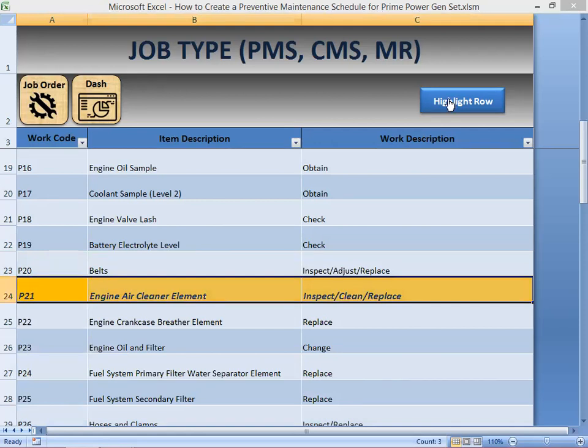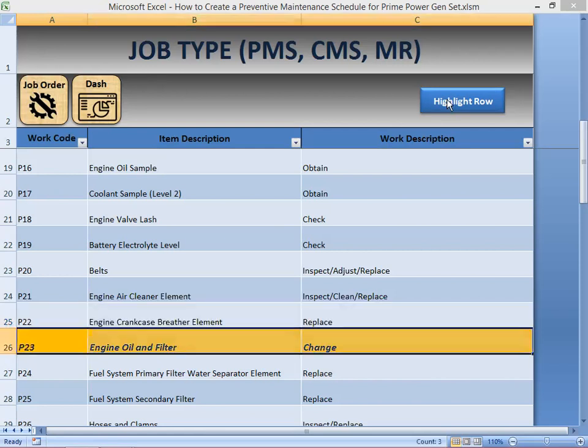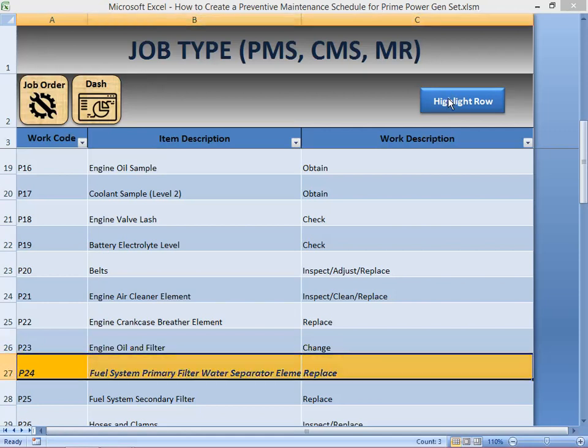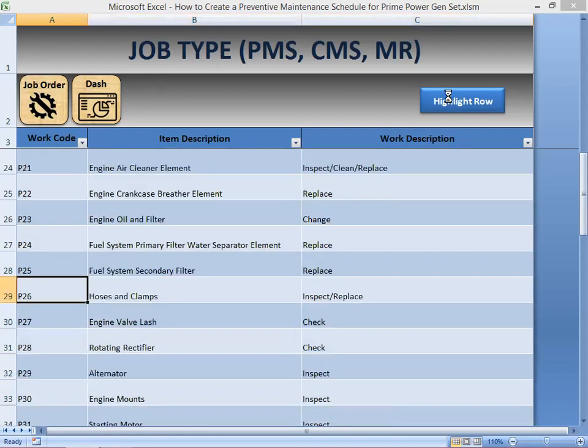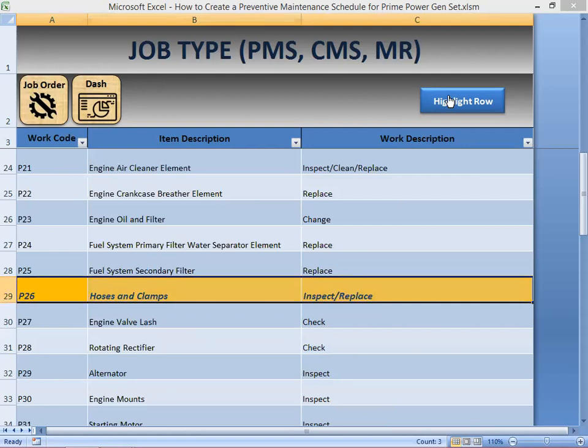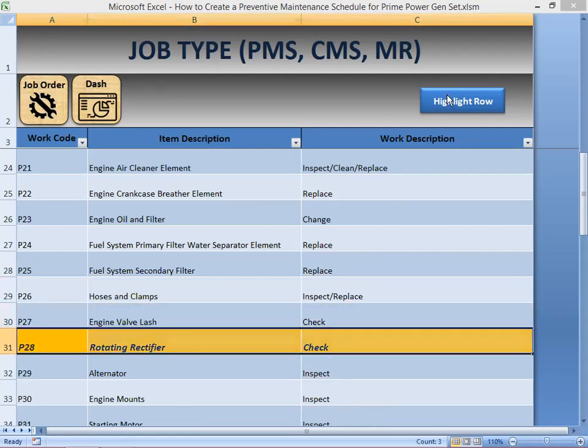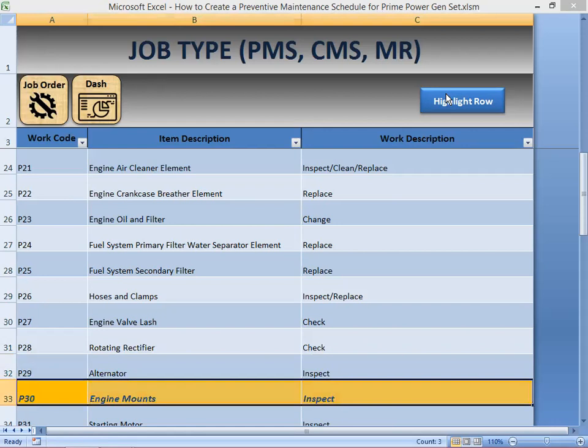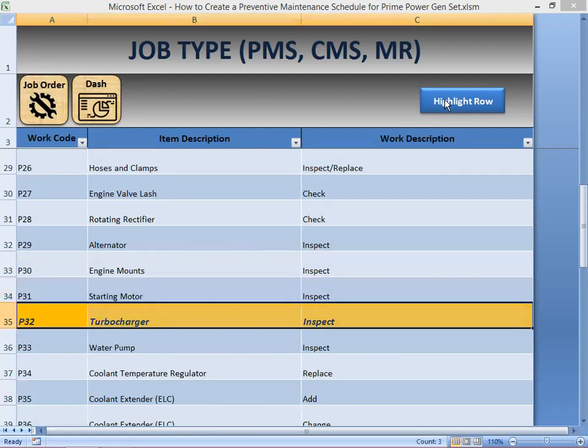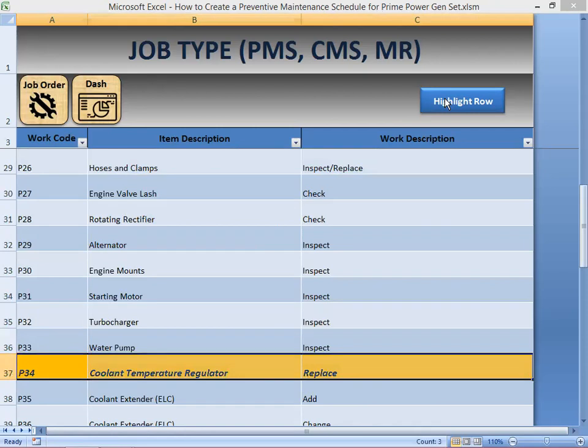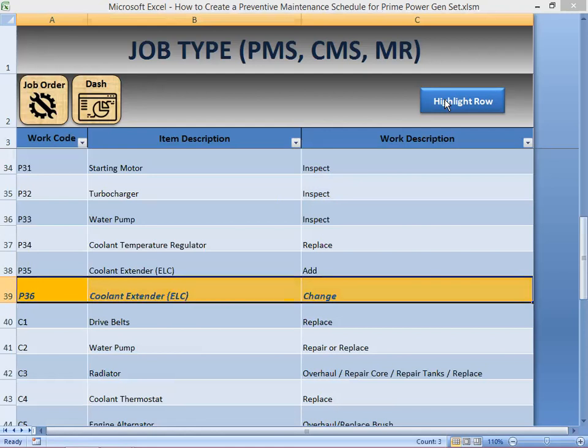Engine air cleaner element, engine crankcase breather element replace, engine oil and filter change, fuel system primary filter water separator element replace, fuel system secondary filter replace, hoses and clamps inspect/replace, engine valve lash check. Rotating rectifier is going to be done by the electrician of the generating set. The alternator, inspect. Engine mounts: sometimes because of the vibration, the engine mounts get loose. You have to inspect that and tighten up some bolts or fasteners.